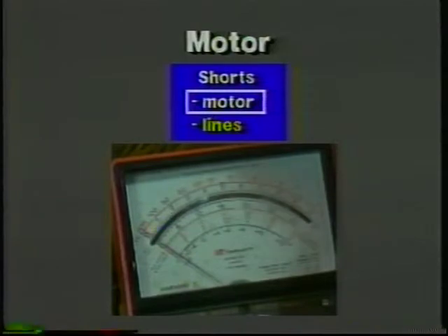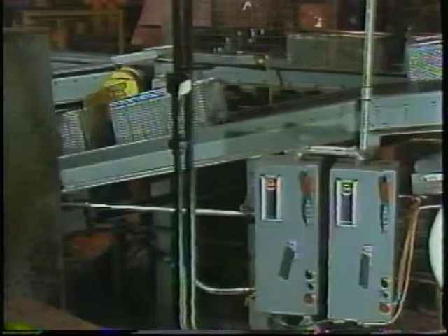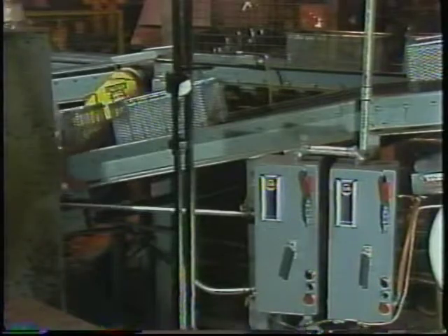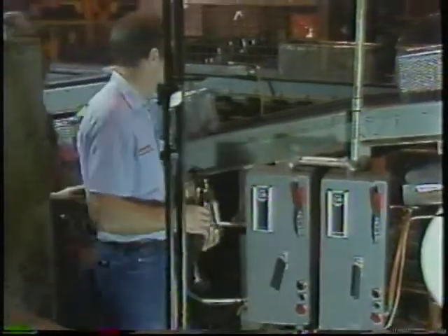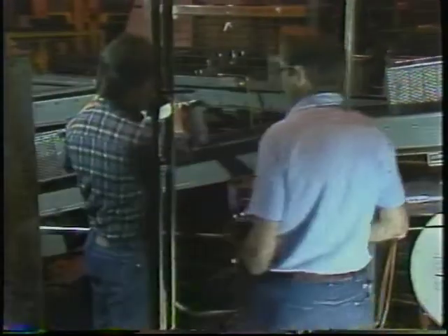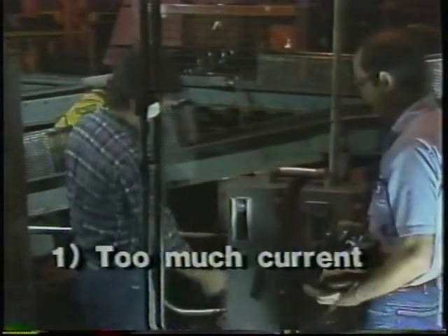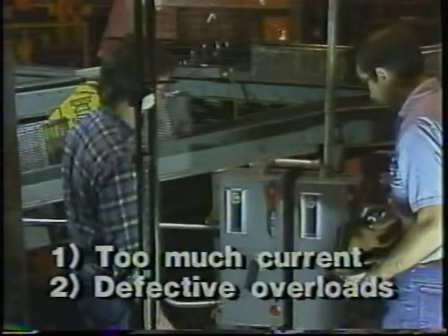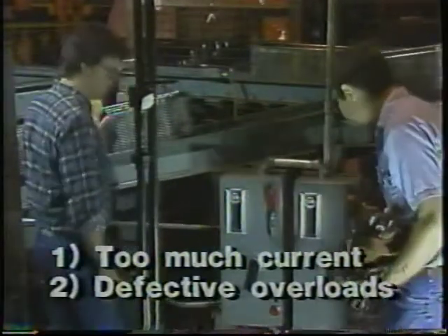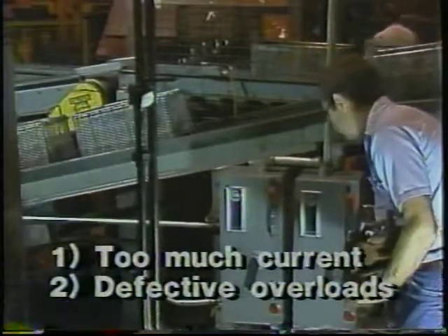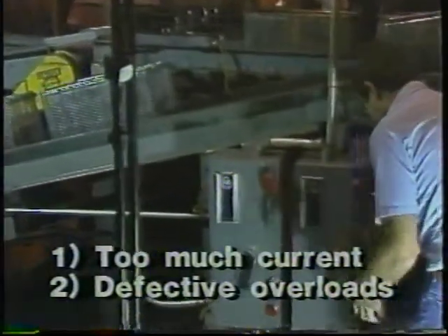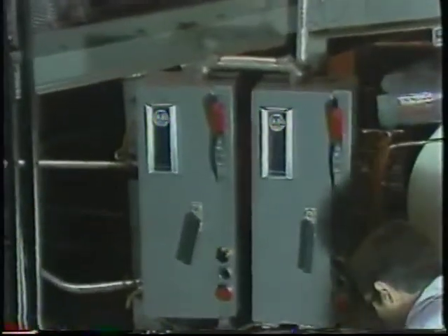Again, the troubleshooting method has quickly and directly led you to the problem. Okay, now suppose you find the most common situation, a tripped overload. The most likely cause is that the motor, for some reason, was drawing too much current. The other possibility is that the overload breaker itself is defective. To eliminate one or the other, you'll have to try restarting the motor.